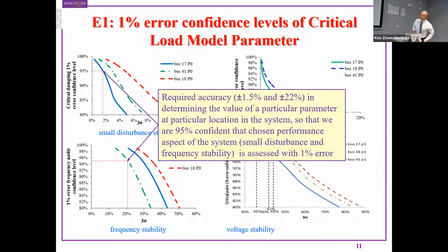When you look at this, the required accuracy varies for different types of stability studies - we did small disturbance, large disturbance, voltage and frequency stability. So how accurate do load models need to be at different locations so that we are happy with the accuracy of our stability studies, because that's ultimately what we want. If I can identify which loads in the system need to be accurate, and which can be modeled with generic models, then as a system operator I can dispatch workforce to those locations and develop accurate models only where it matters, not everywhere else, because that won't affect system behavior.